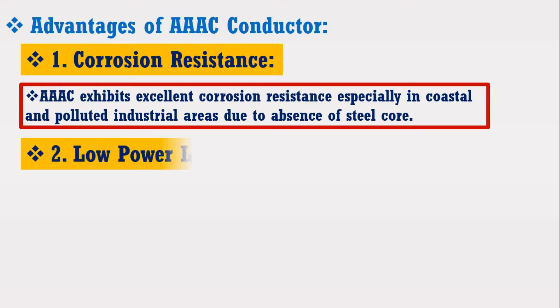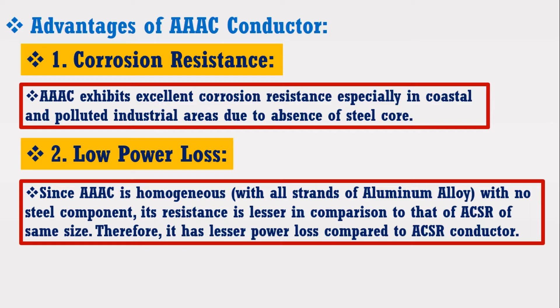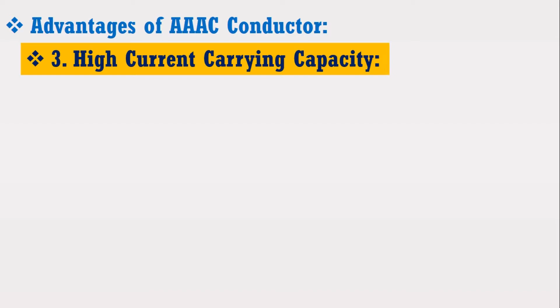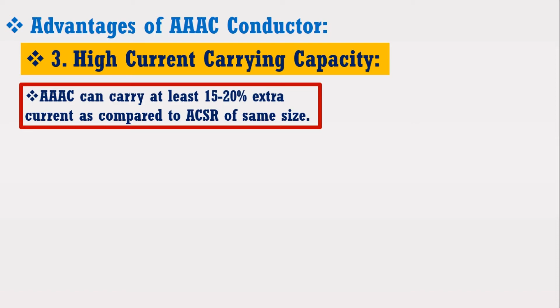Number 2. Low power loss. Since all aluminium alloy conductor is homogeneous with all strands of aluminium alloy with no steel component, its resistance is lesser in comparison to that of ACSR of same size. Therefore, it has lesser power loss compared to ACSR conductor. Number 3. High current carrying capacity. All aluminium alloy conductor can carry at least 15 to 20% extra current as compared to ACSR of the same size.